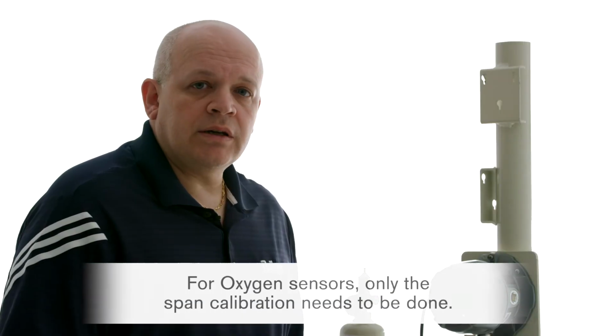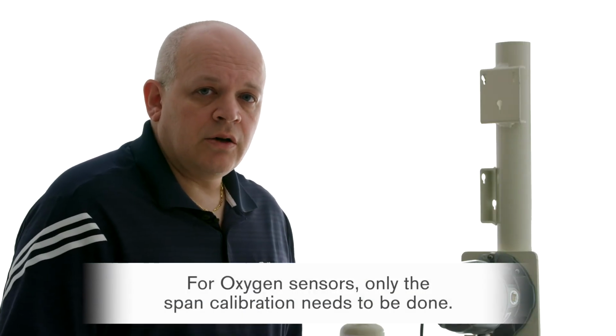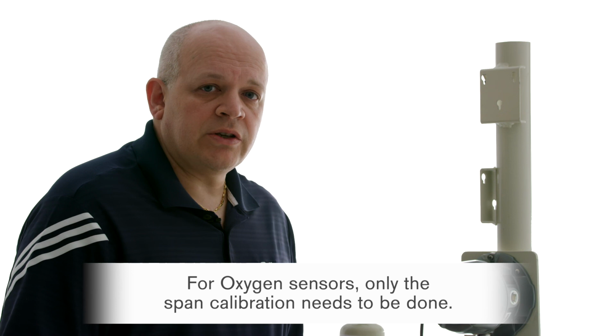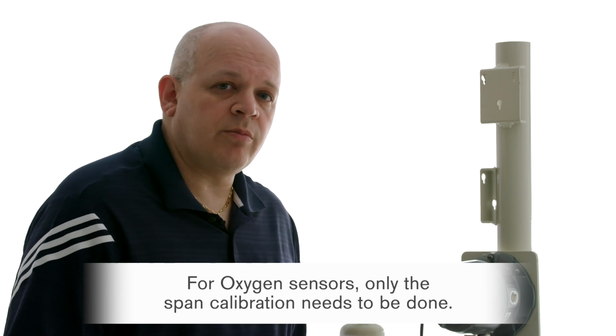The zero can be done either with fresh air or a zero air calibration cylinder, which is 20.9% by volume of oxygen, or you can use nitrogen. That should be your last resort. We prefer to use either fresh air or zero air bottle, but if you only have nitrogen, that can be used as well. So for us, we're going to do a zero with fresh air, and we're going to calibrate the span with a 50 ppm carbon monoxide cylinder.